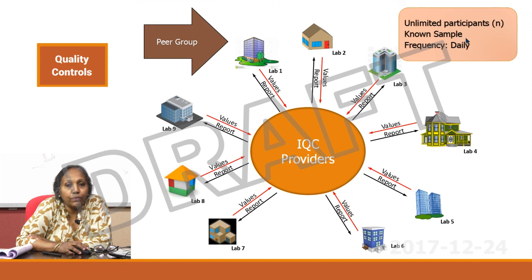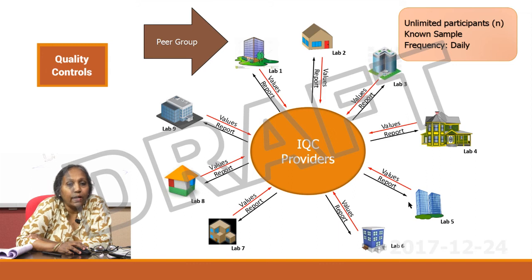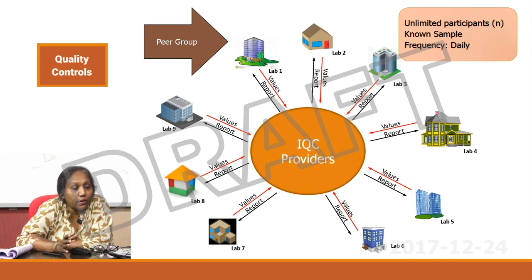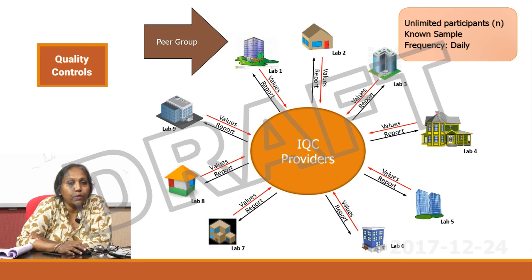This is how the peer group mechanism works. The IQC providers give you known materials — these are not blind samples as in EQA where you do not know the value. With IQC you already know the value because it is provided with your IQC material. You analyze, everybody else also analyzes, and you pool in your values. The IQC provider finds a mean and lets everybody know what the mean is and how much you are straying away from the mean, giving you an idea about your inaccuracies.